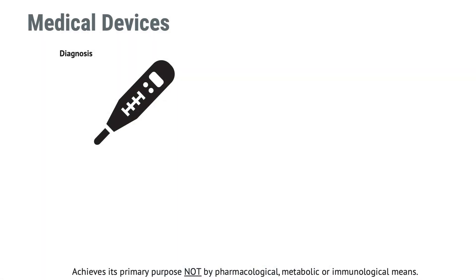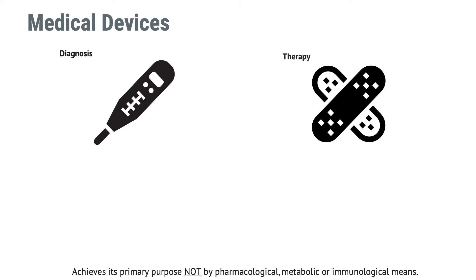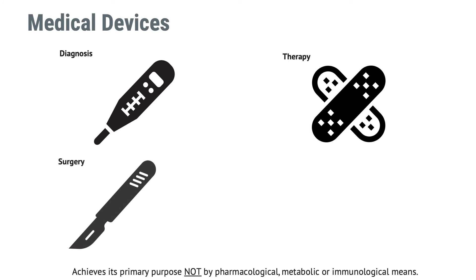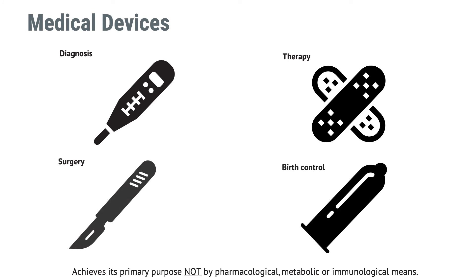So what all this means is that if you intend your product to be used for diagnosis — for example, a thermometer — therapy, which could be band-aids or surgery, let's say a scalpel, or as a contraceptive like a condom, and your product does not achieve its primary purpose by pharmacological, metabolic or immunological means, it is probably a medical device. Even if your product is assisted in its function by a medicinal product, it can be a medical device as long as the primary purpose is not achieved by the pharmaceutical component. Please note that also standalone software and mobile phone apps can be medical devices, assuming they meet the criteria of being a medical device.